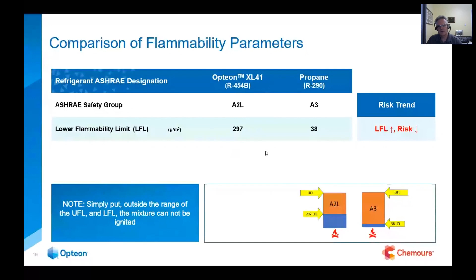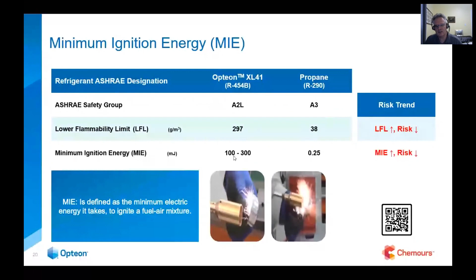The next thing we're going to show is minimum ignition energy. How much energy does it take to ignite this combustible mixture? With propane, you can see you need very little energy to ignite it, a static spark from a carpet as an example. Whereas with the A2Ls, in this case 454B, it's way more energy. So this is good. We want something that's harder to ignite than propane.